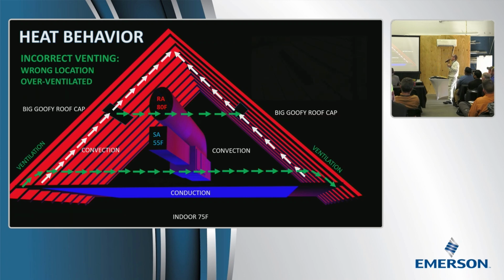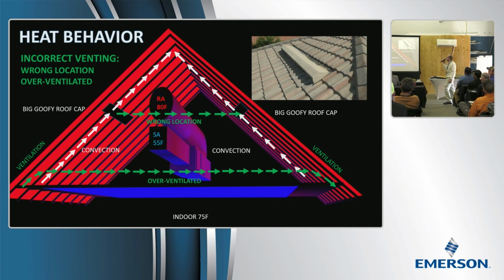What do we really build? Big, goofy roof caps. And the big, goofy roof caps are a way to convey hundreds of CFM of airborne moisture and cross ventilation through the attic. So some people say, well, doesn't it make the attic cooler? If you want to make the attic cooler, anticipate the ducts are going to sweat. That's where we started, right? What was the biggest difference? The biggest difference was the temperature of the air around the duct, remember? That makes a big deal. It only makes a little deal what the air is on the inside of the duct. So this is a bad situation.